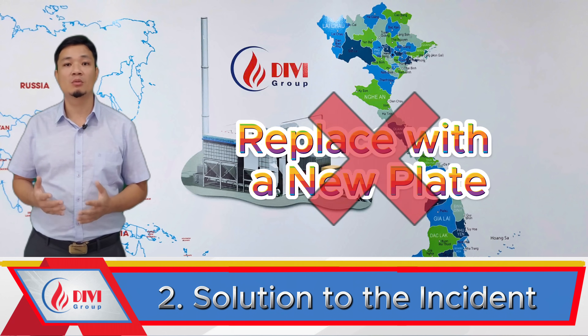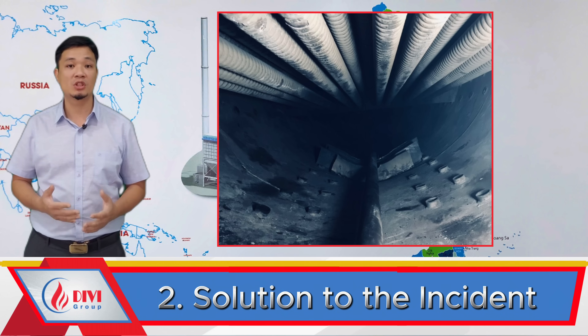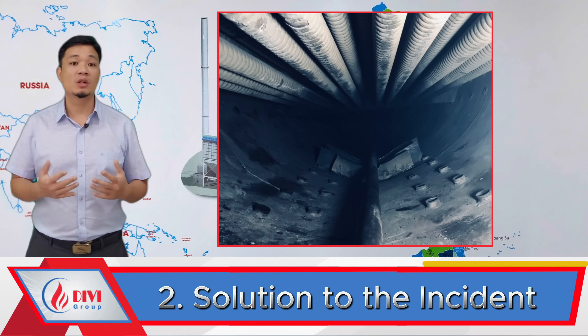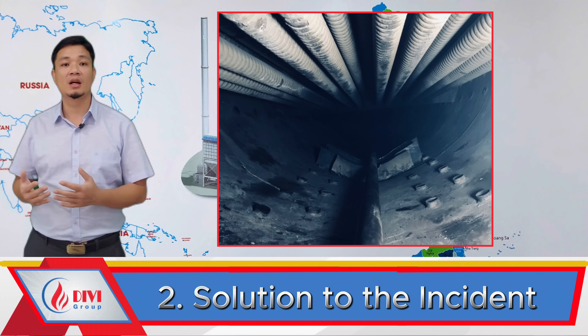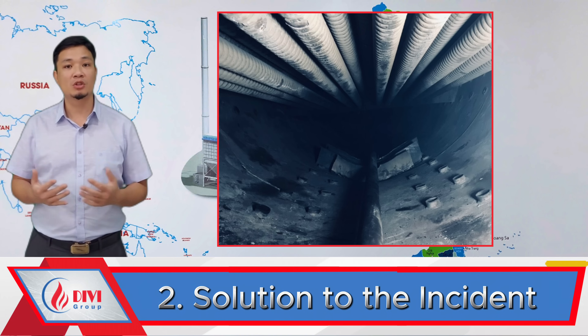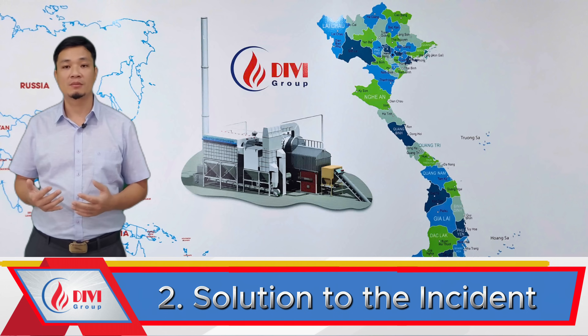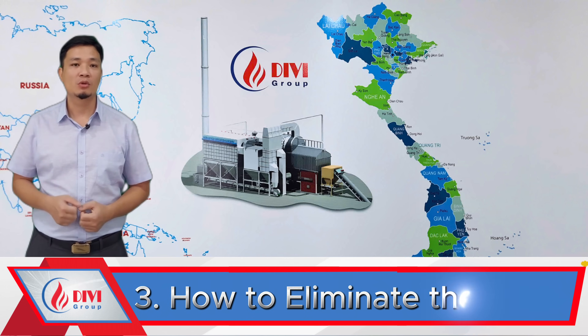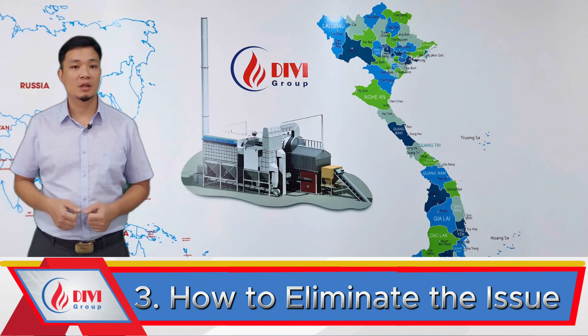So we went with the reinforcement plan, installing vertical stiffener bars on the bulged area. After a full night of hard work, DIVI's team completed the reinforcement. The client then conducted a hydrostatic pressure test before resuming operations, and the boiler returned to normal working condition.